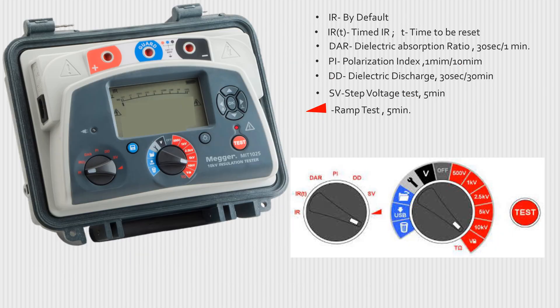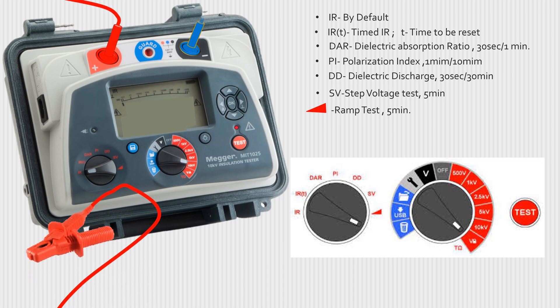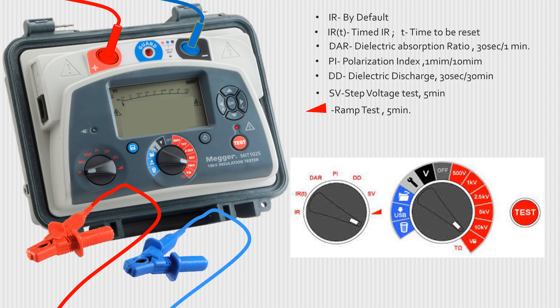This is a picture of a digital megger. The red lead is to be connected at the positive indicated port and the blue lead at the negative indicated port. A guard connection may or may not be used. The red clamp and blue clamp are to be connected at two points between an insulation whose insulation resistance is to be measured.